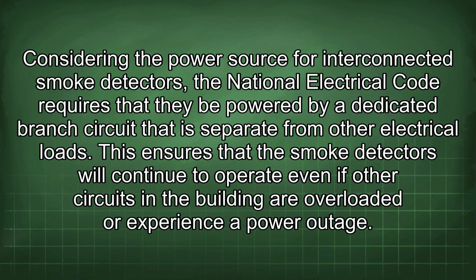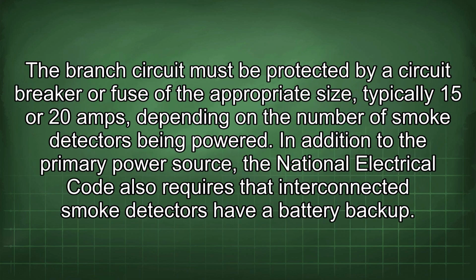Considering the power source for interconnected smoke detectors, the National Electrical Code requires that they be powered by a dedicated branch circuit that is separate from other electrical loads. This ensures that the smoke detectors will continue to operate even if other circuits in the building are overloaded or experience a power outage. The branch circuit must be protected by a circuit breaker or fuse of the appropriate size, typically 15 or 20 amps, depending on the number of smoke detectors being powered.